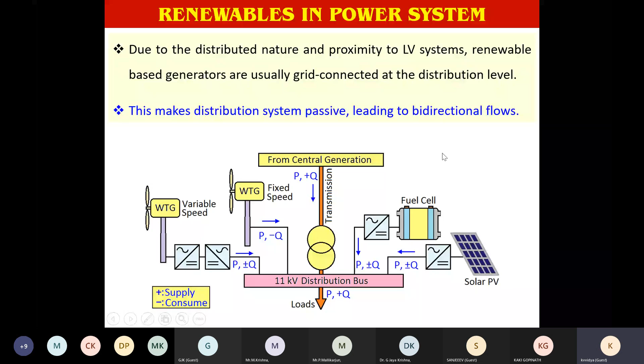But because of the renewable energy connected to the low voltage grid, now your distribution system is also becoming active. Active means they are now capable of giving fault current. When a fault occurs, there will be unusual behavior as compared to the original design, and your buses are not designed for that. So what are the problems we have to consider before connecting a renewable resource in the power grid?